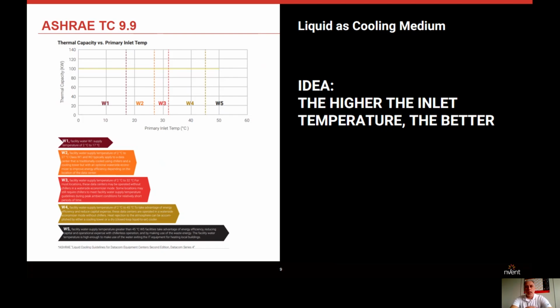Now we talked a little bit about liquid cooling, and ASHRAE came up with some new ideas. Frankly speaking, I would break it down to the main idea: the higher the water inlet, or the higher the liquid inlet temperature, the better. What does that mean? It means you need less energy upfront to cool down the water. Every degree that you can increase the inlet temperature of your liquid, the more energy you save upfront. And that's the main idea behind all these documents. Keep that in mind. We will come back to that.